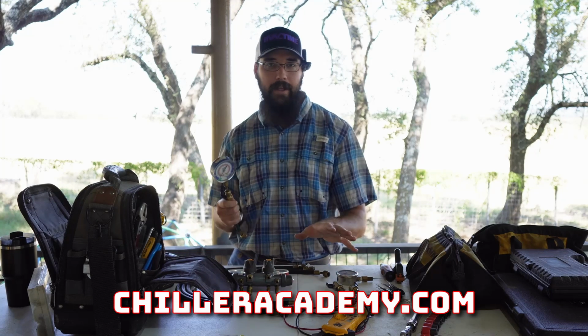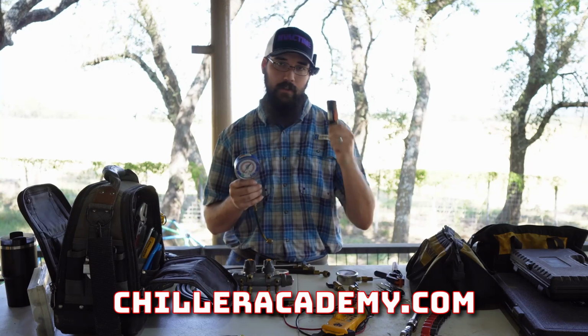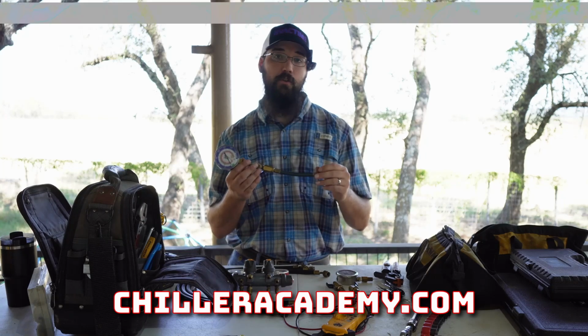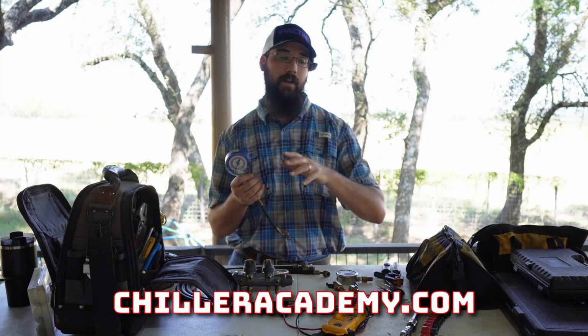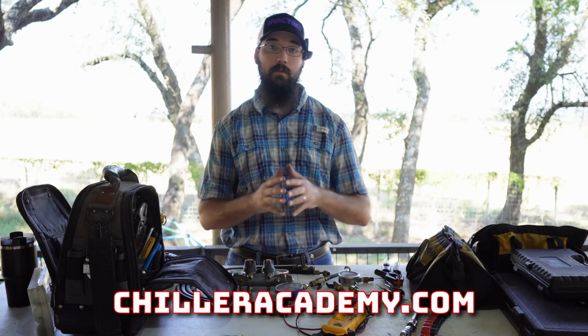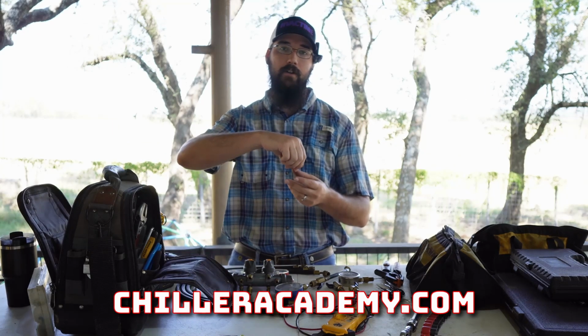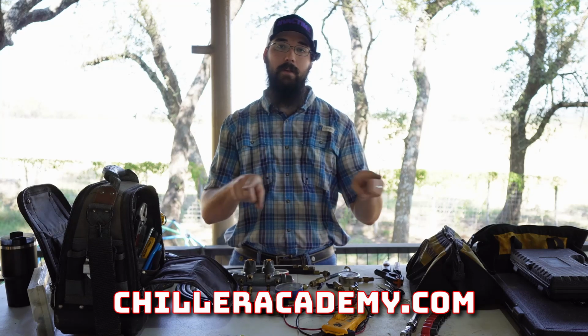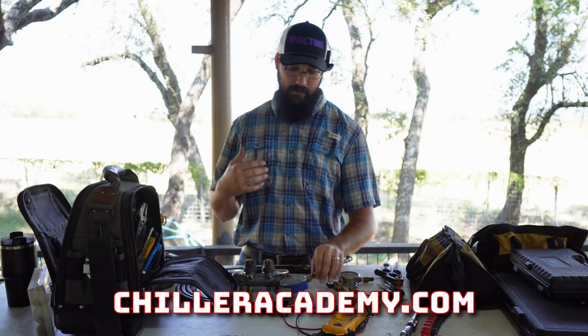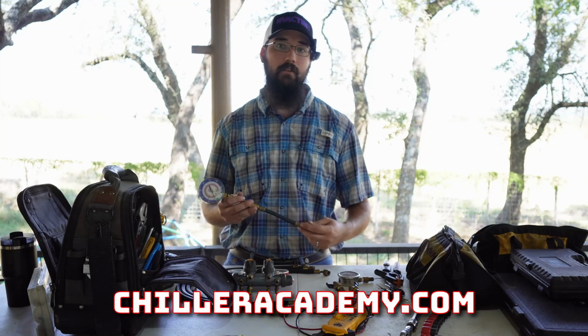Have a set of 4 ports in case you ever need it. But what I did was I moved to stubby gauges, and then eventually that was just a precursor to the Bluetooth. And then I would use brass T-fittings. So if I needed to connect hoses together or run multiple lines, tanks, whatever the case may be, or needed it longer, I would use these T-fittings. And if I only needed it as a coupling, I could just put a Schrader cap on the third port, and then it just became a straight pass-through coupling. So those are just some things that I practice and how I connect my hoses. So you won't see me use a set of manifolds really ever.